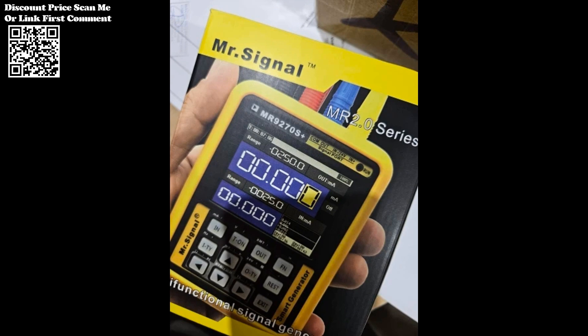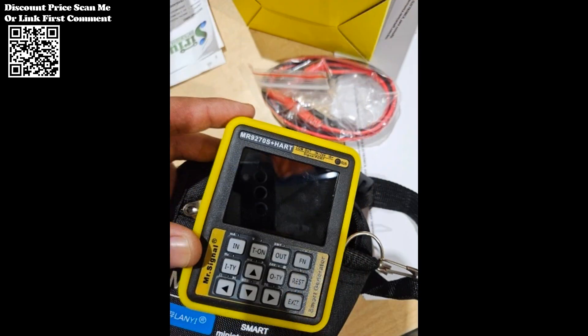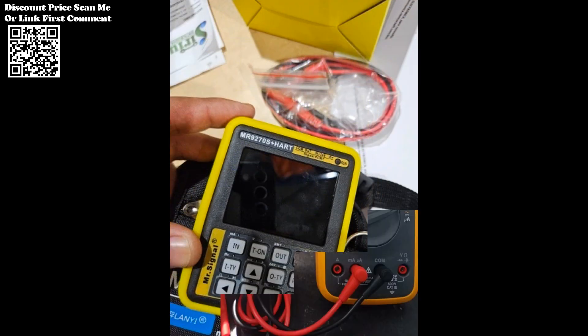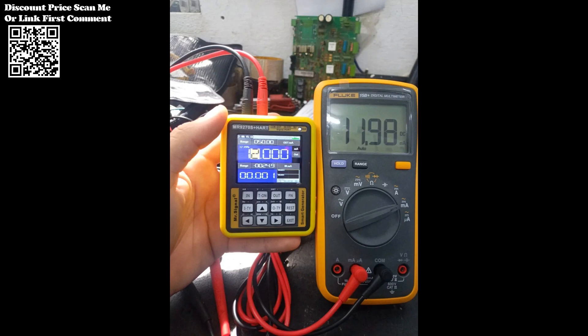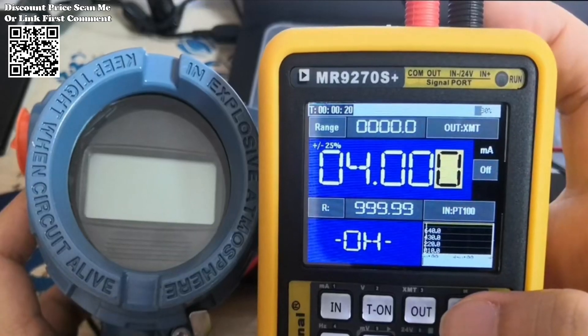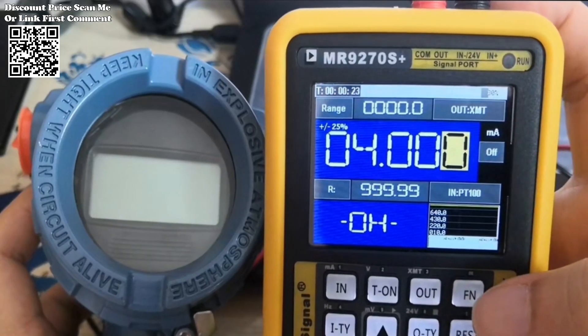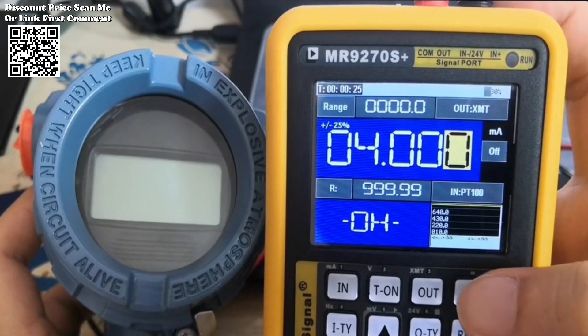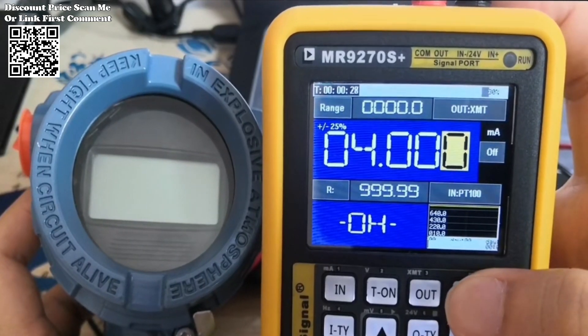Feature 4: Preset values. 9 sets of commonly used signal values can be preset for fast output. Feature 5: Convert the input signal into an output signal. For example, convert the input frequency signal into a current signal and convert the input range from 0 to 1000 hertz to 4 to 20 milliampere.